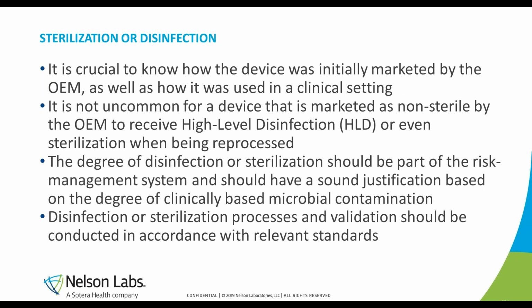Sterilization and disinfection processes and associated research should be conducted to understand how the device was initially marketed by the OEM, as well as how it is used in the hospital or clinical setting. Due to the exposure in a hospital setting, devices may run the risk of being contaminated with organisms associated with healthcare-acquired infections. It's not uncommon for a device that is marketed originally as non-sterile to receive high-level disinfection or even sterilization when being reprocessed by a third party to eliminate the possibility of transmission of these infectious organisms. Sterilization or the degree of disinfection should be part of the risk management system and be based on the substantial equivalence or based on the risk potential of microbiological contamination. Disinfection and sterilization processes and validation should be conducted in accordance with relevant standards.